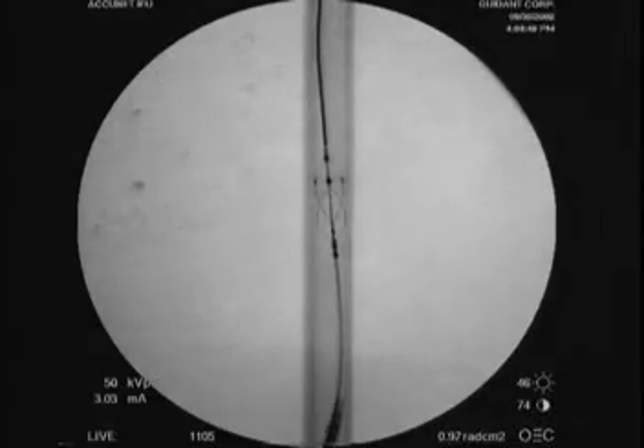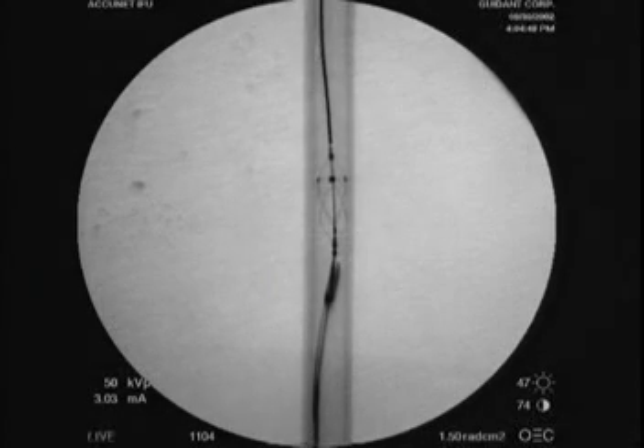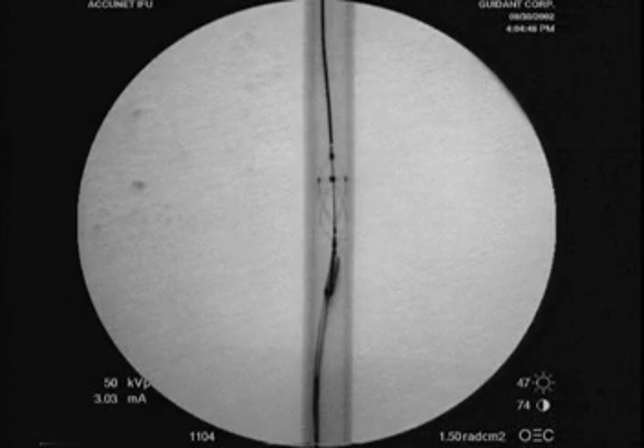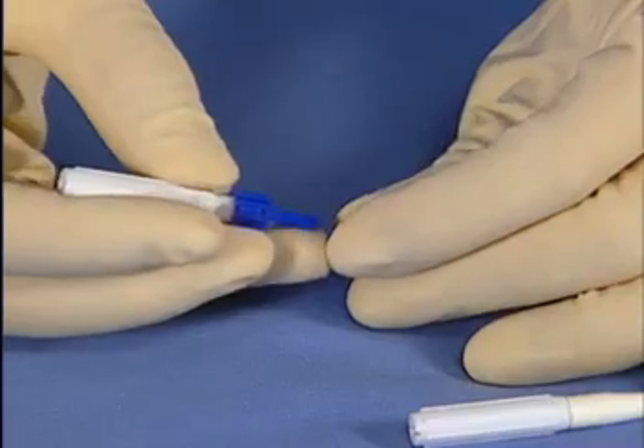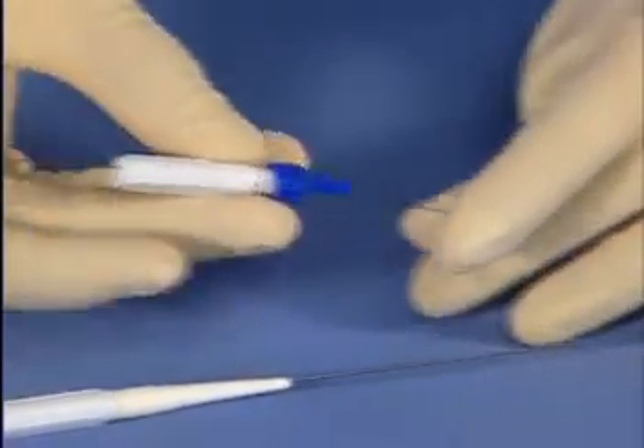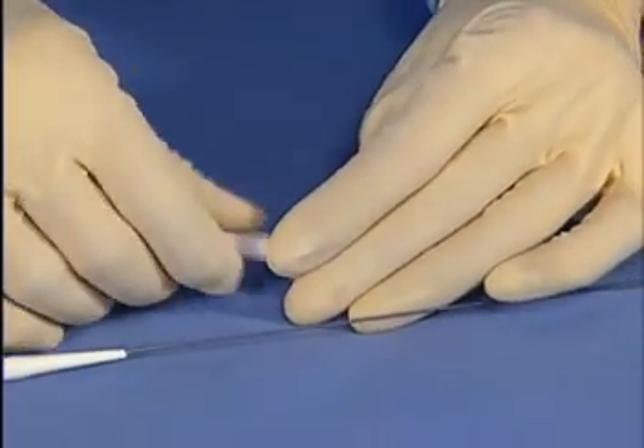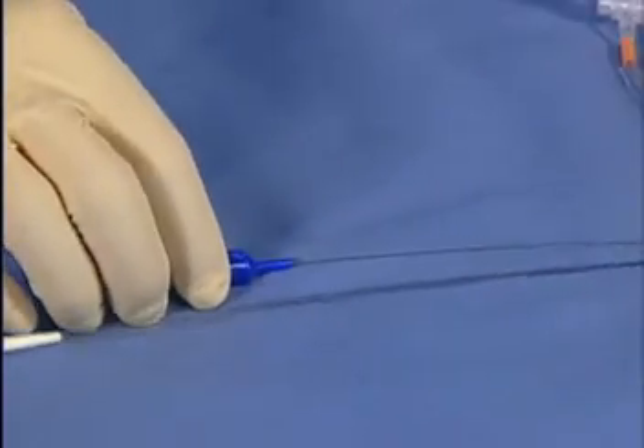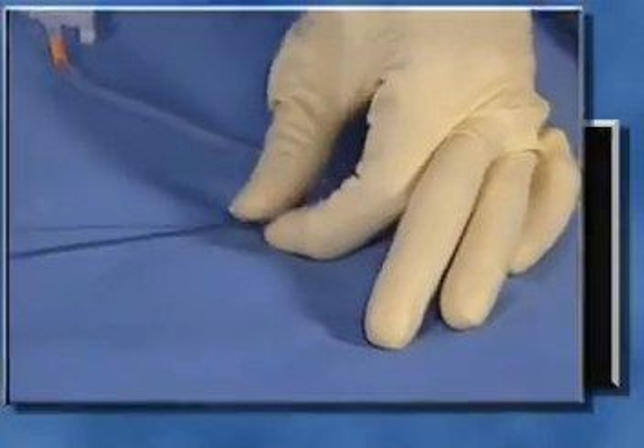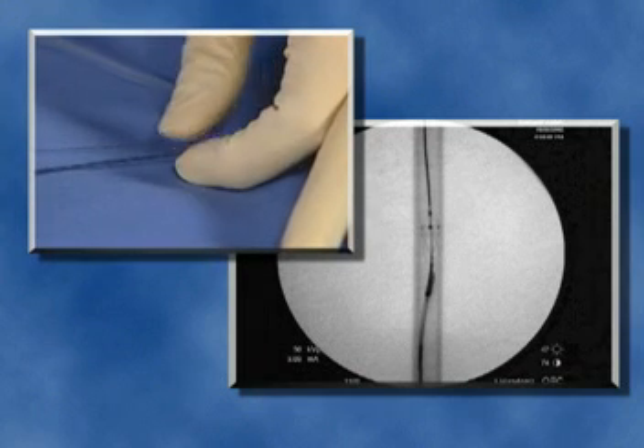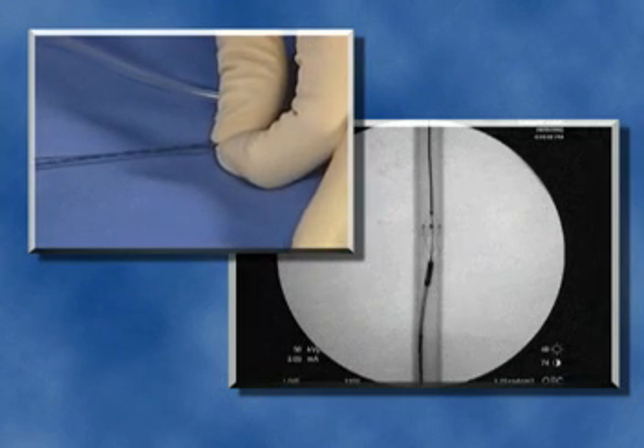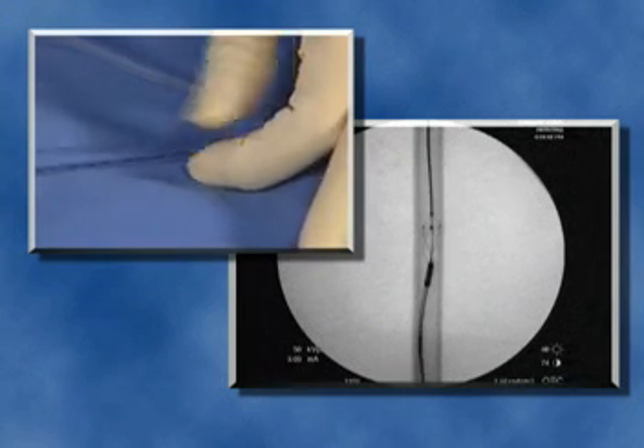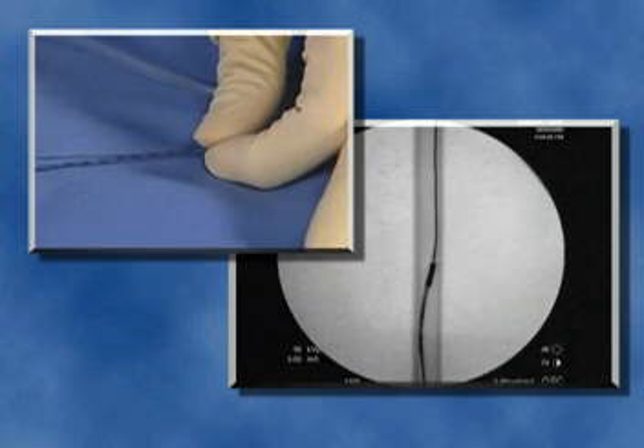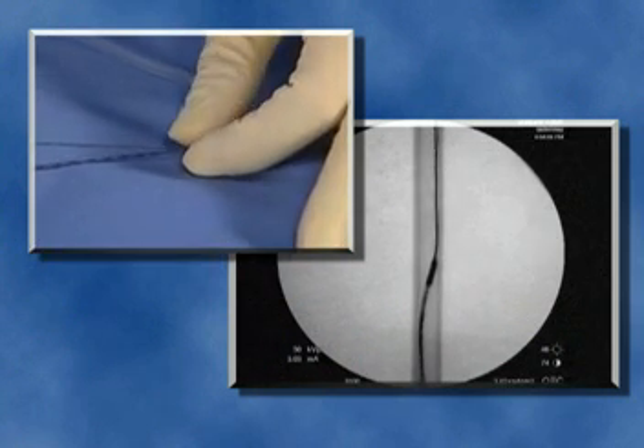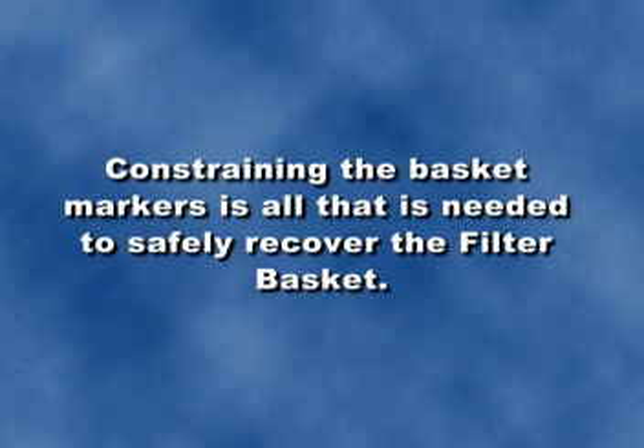until the tip of the catheter meets the radiopaque proximal bushing of the filter basket. Attach a torque device to the guide wire. Then gently pull on the wire of the filter basket and at the same time advance the recovery catheter until the 4 basket markers come together. Constraining the basket markers is all that is needed to safely recover the filter basket.